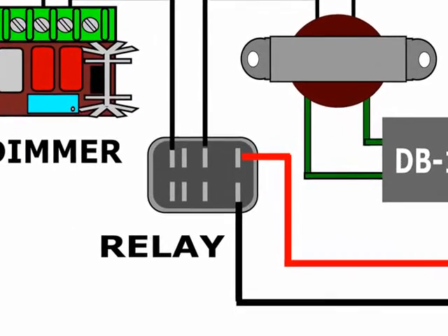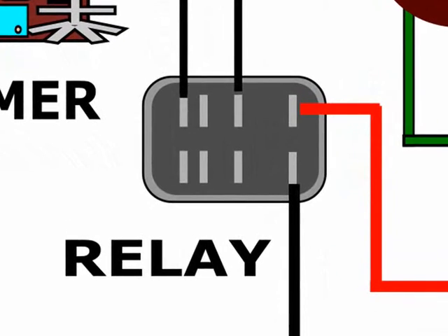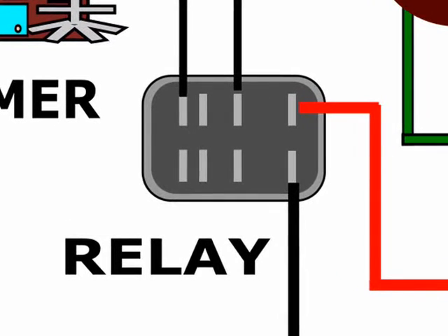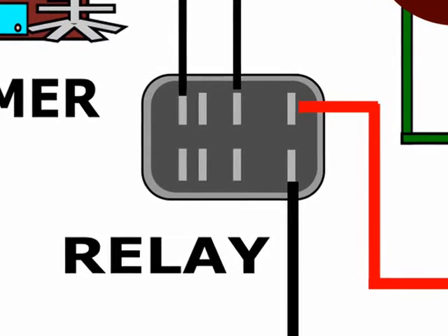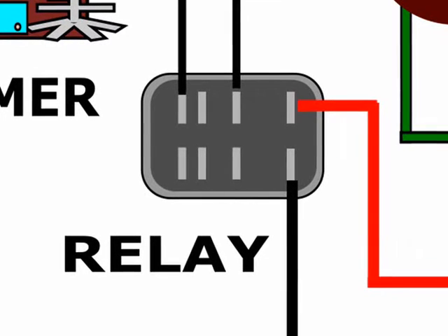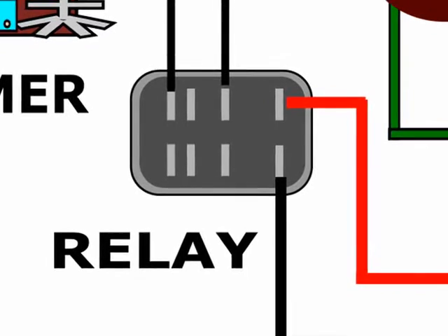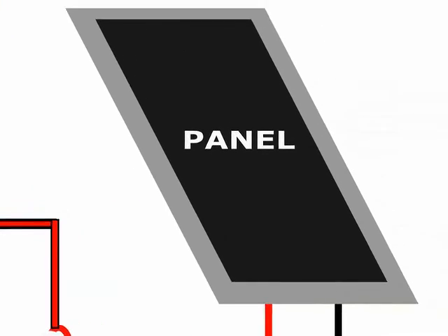An additional note about the charger is that it turns on only at night by means of a relay, normally intended for 110 volts AC, energized by the voltage produced by the solar panel. When the sun shines, the relay is energized and disconnects the primary of the charger transformer, so that it does not interfere with the normal charging of the solar power system.